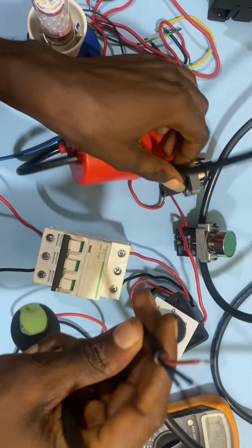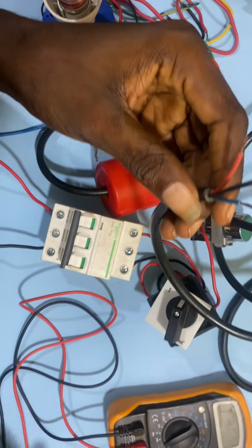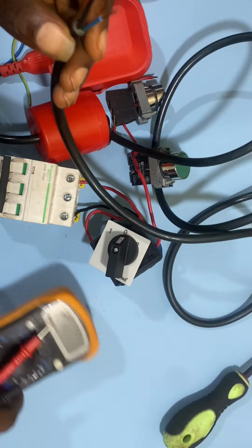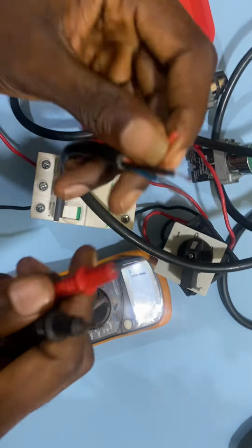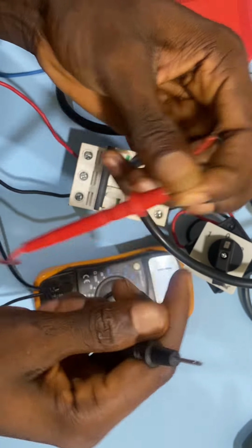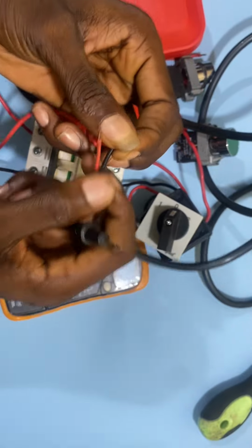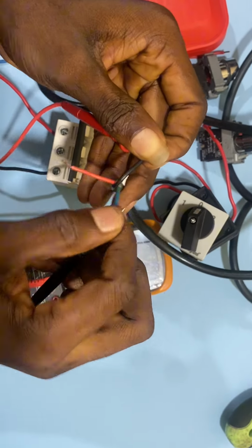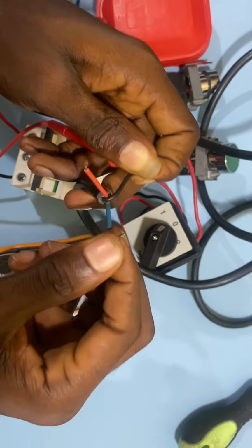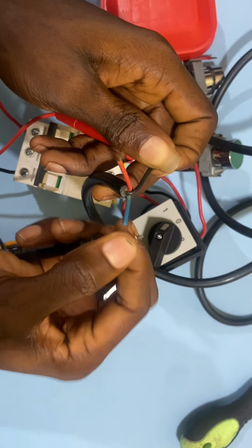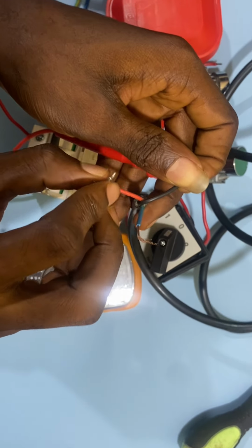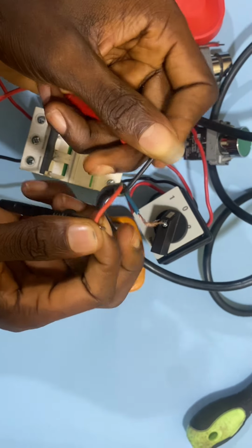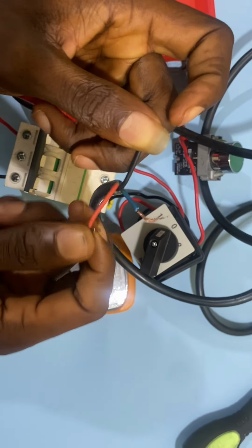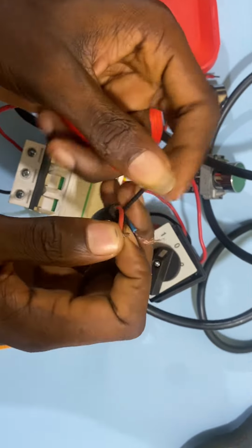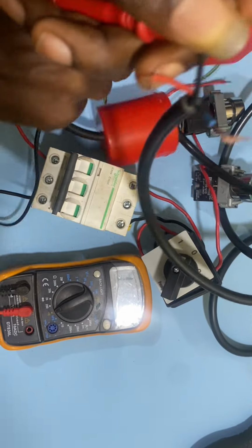So the next thing is to identify these terminals of this flow switch. So I'm going to use my meter to identify the terminals of the flow switch. So this is my common, to show you that this is the common. So I keep this here. It is not reading, therefore this contact of the flow switch is normally open. This one is reading, meaning that this contact of the flow switch is normally closed. So that means as it's dropping down, this is the position that is reading at this position now.